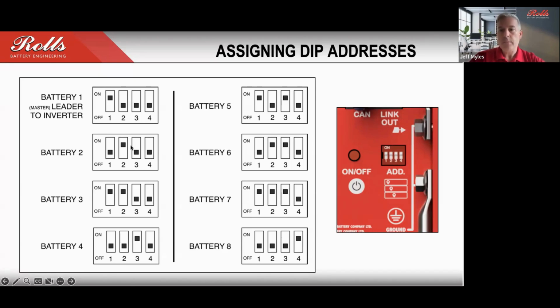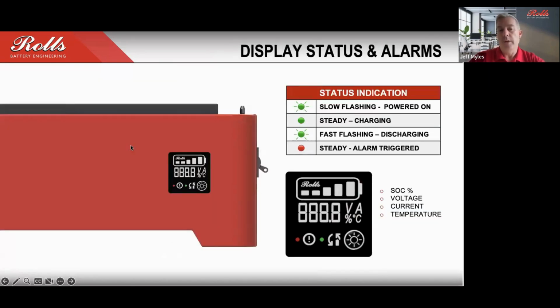On the front of the unit, I mentioned before that you would be able to see status information when you turn on the BMS switch. Once that unit is connected and the stack is assembled and connected to the inverter, in the case where you're doing a charge, for example, the status light on the front of the unit is going to change depending on the conditions. If you're doing a charge or a discharge, and you run into a situation where the BMS has triggered an alarm, then that's going to be indicated on the front of the unit.